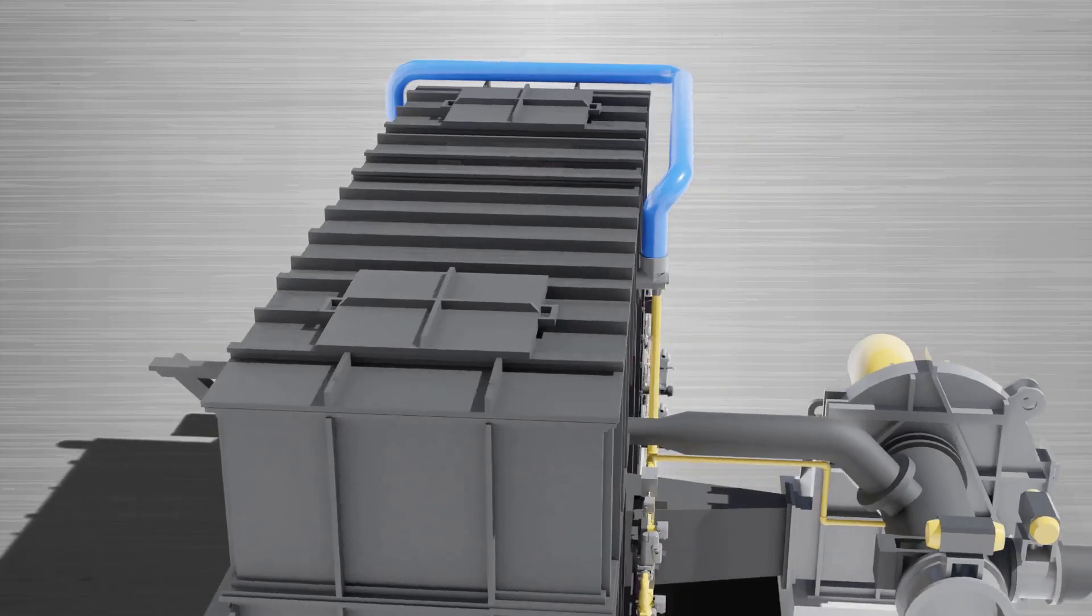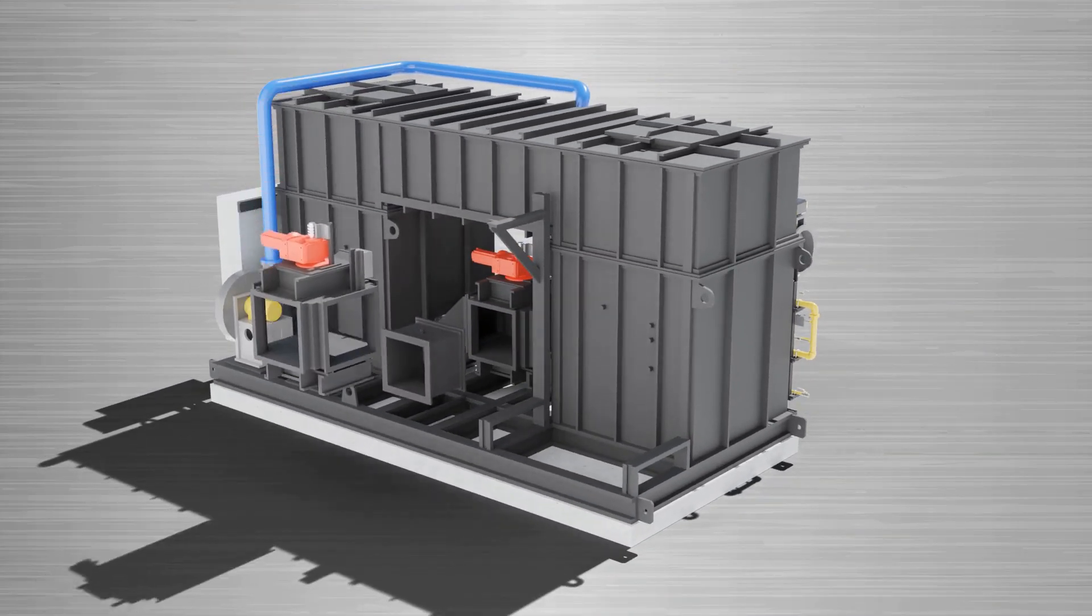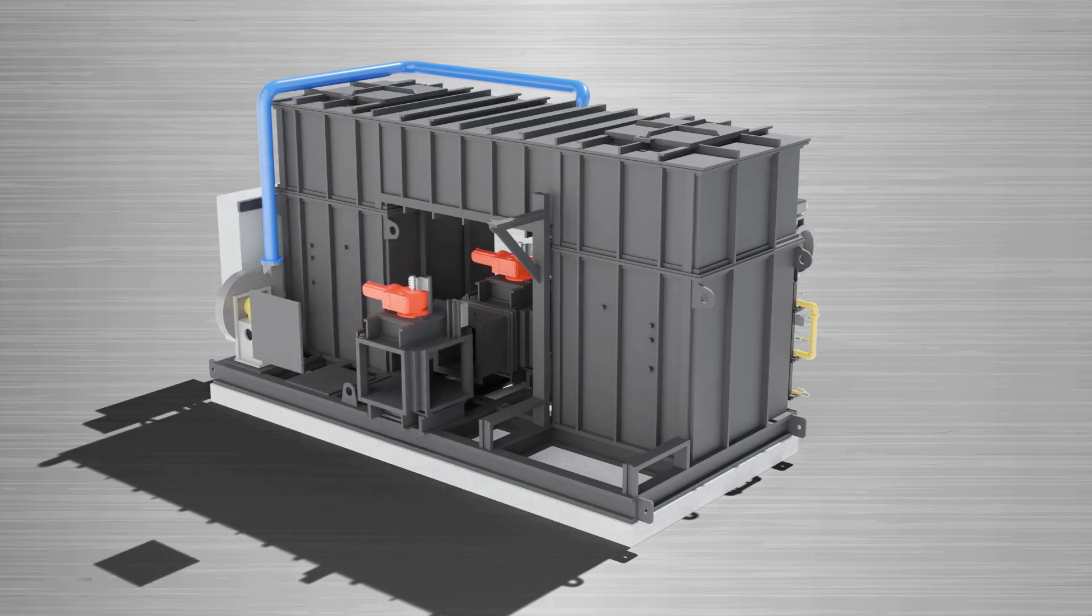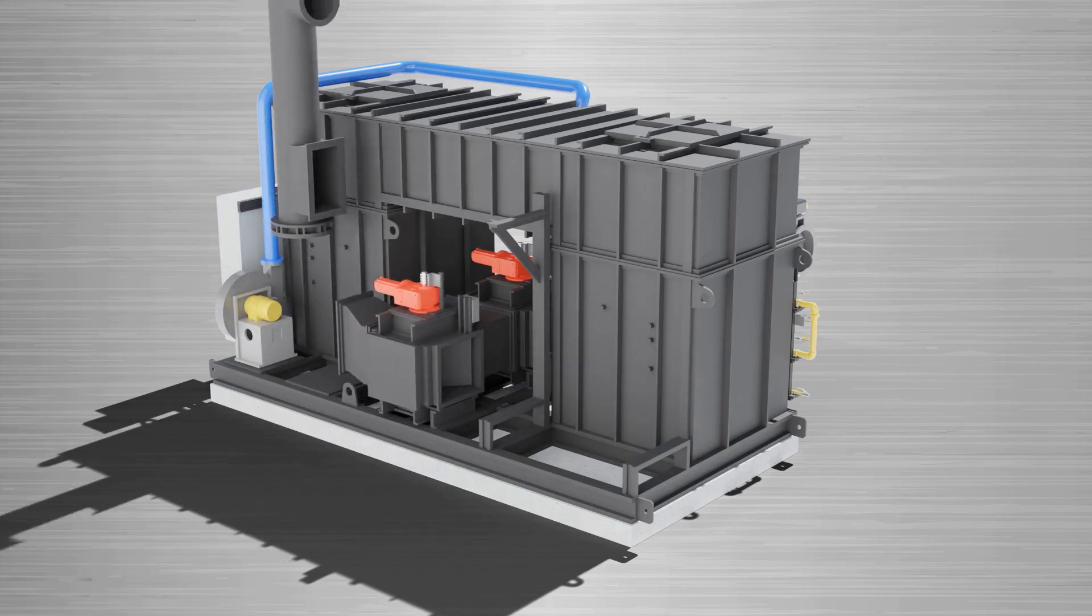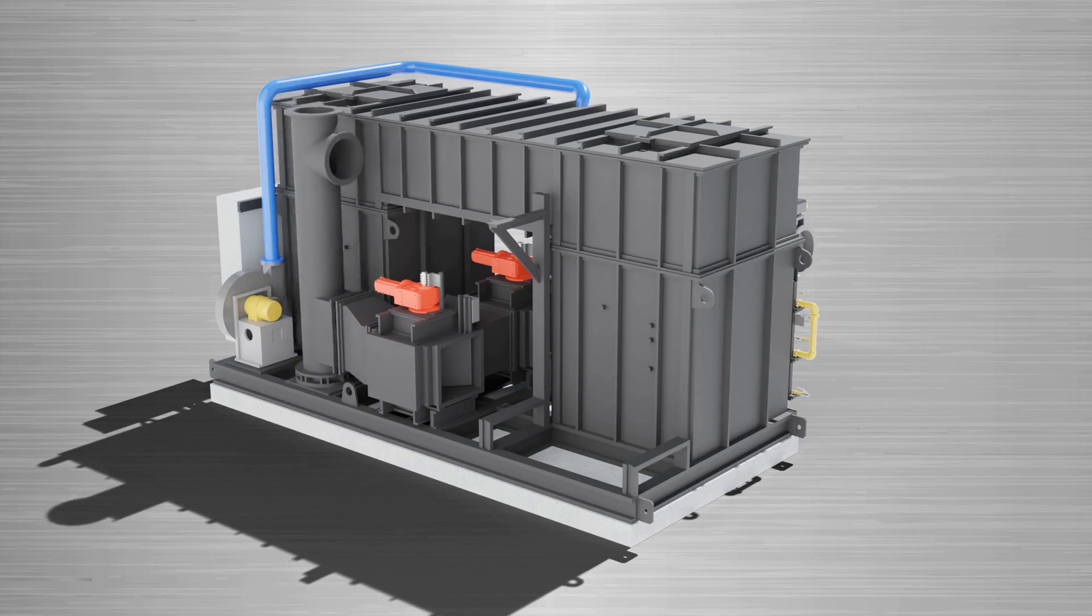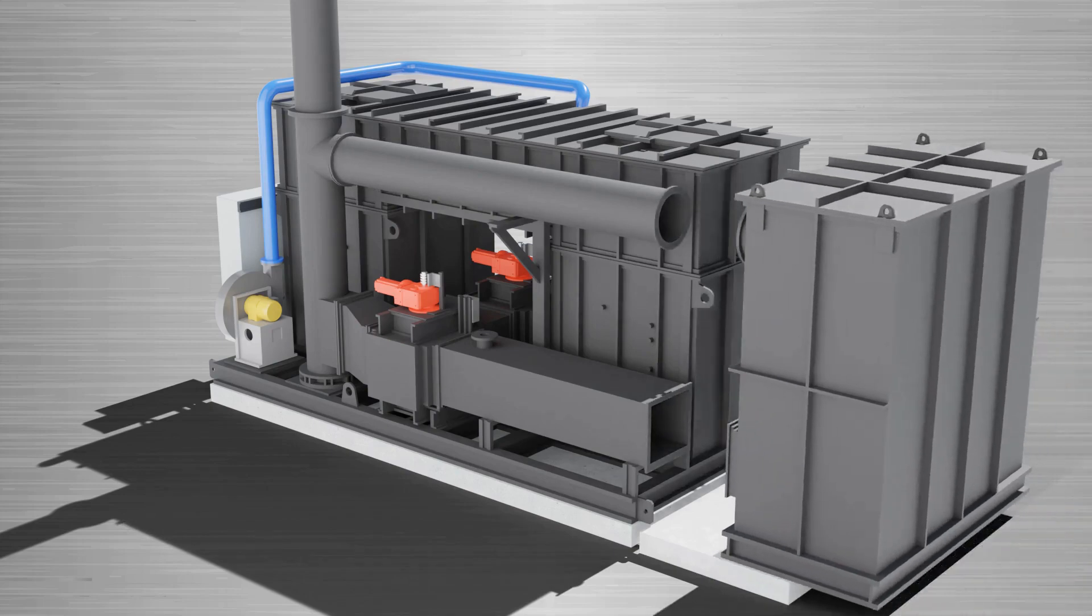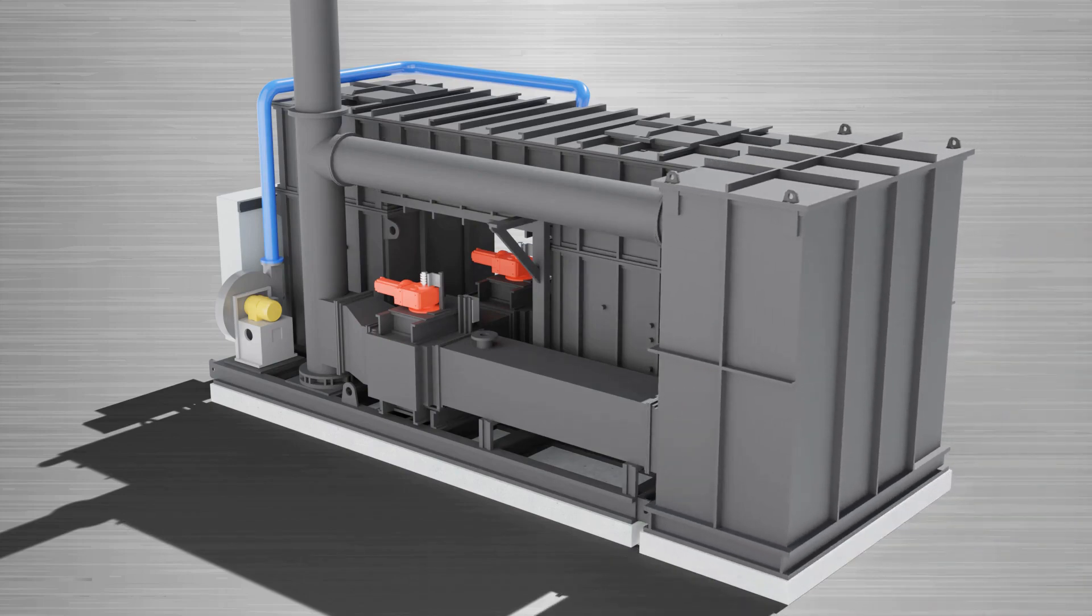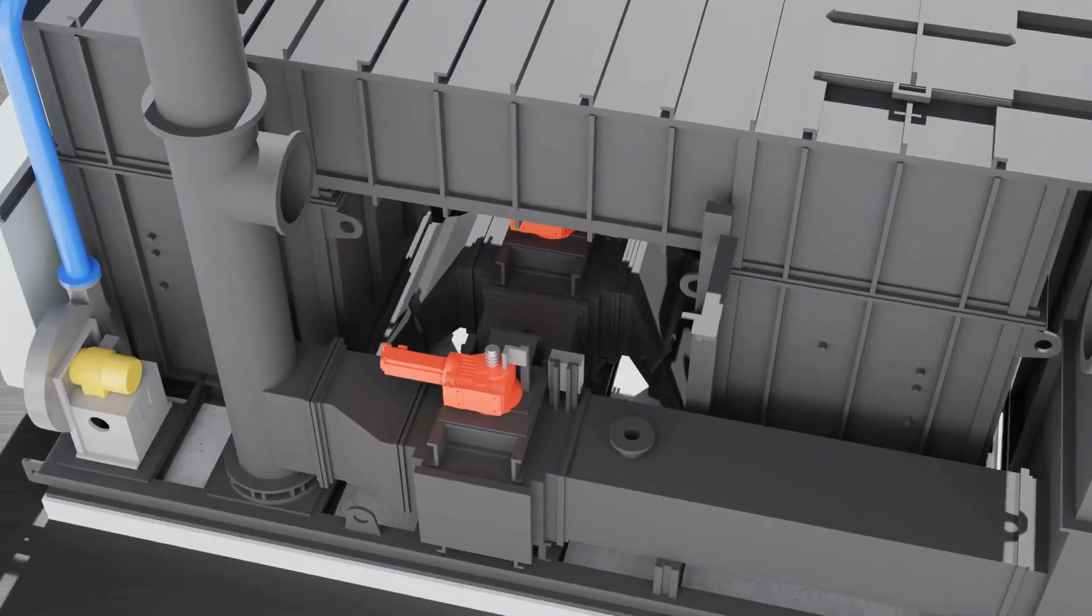The second add-on RTO option is a puff capture system. This system increases the destruction performance of the RTO from 98% to greater than 99%. The system consists of a second QS valve, puff capture chamber, and additional ductwork. The puff capture system collects puffs of untreated emissions that occur when the QS valve transitions.